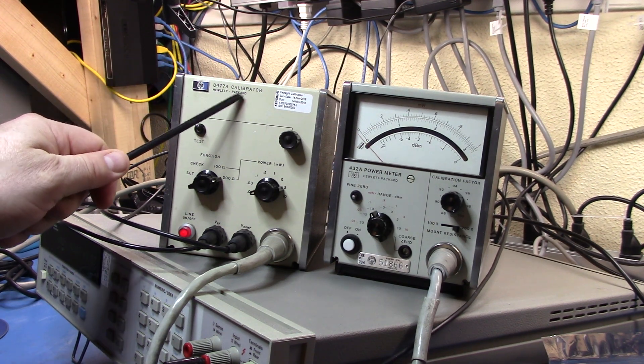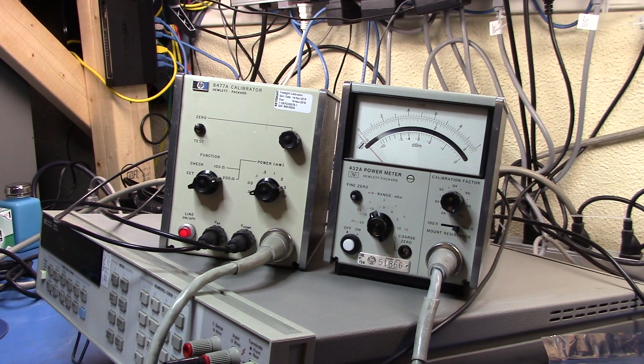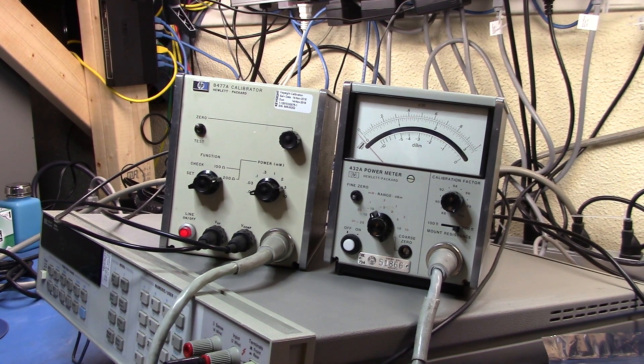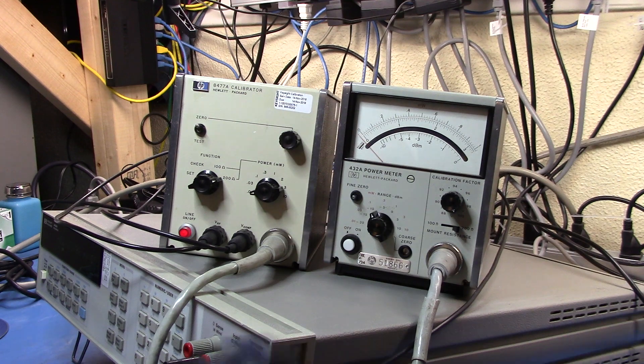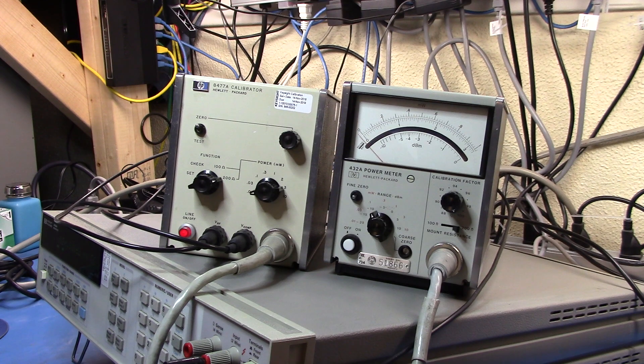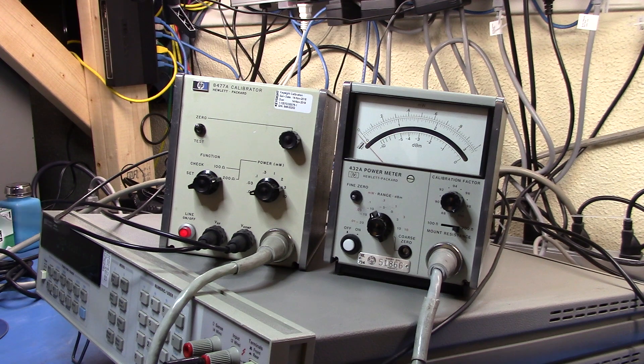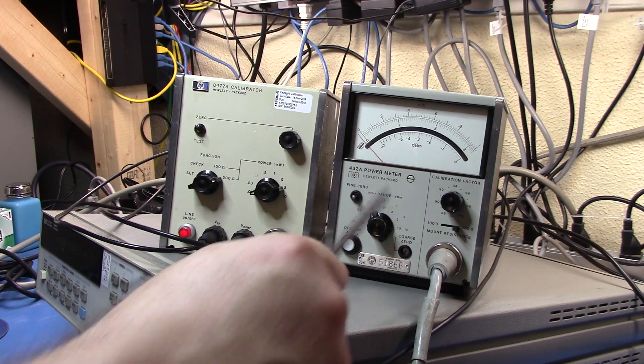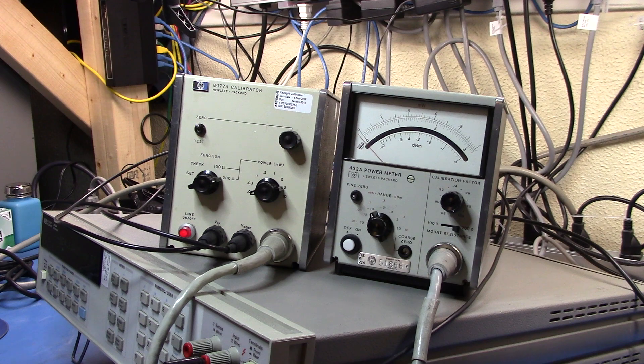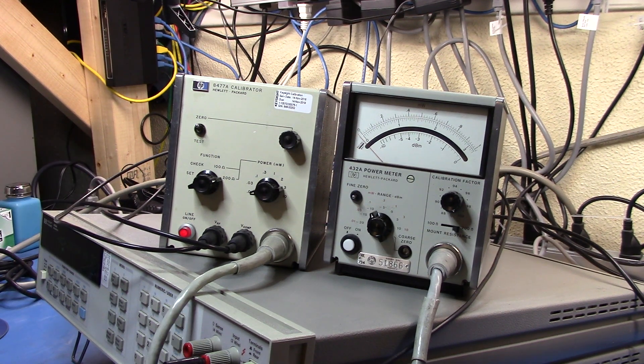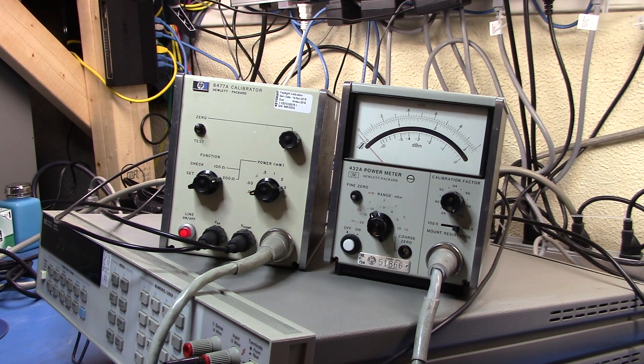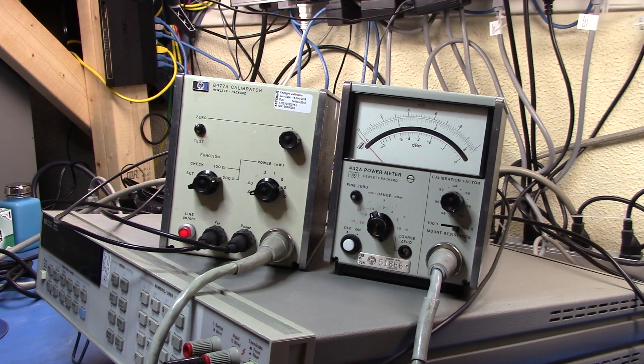I just got this guy back from Keysight where they had tested it, adjusted it and calibrated it. I've got my two sensors back from them as well. I've got several of these power meters here, so I thought it would be cheaper for me to get the calibrator calibrated and then do the checks on the power meters myself. I also have my 3458A back that's been calibrated as well.